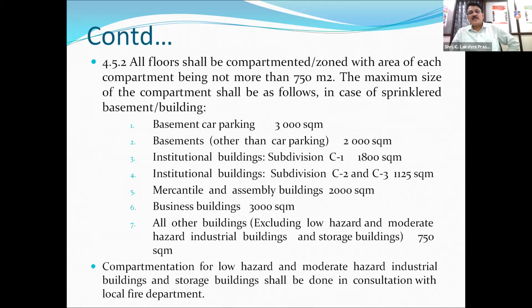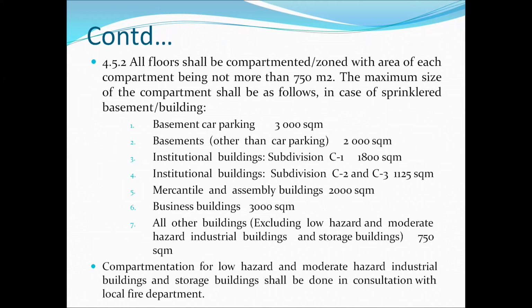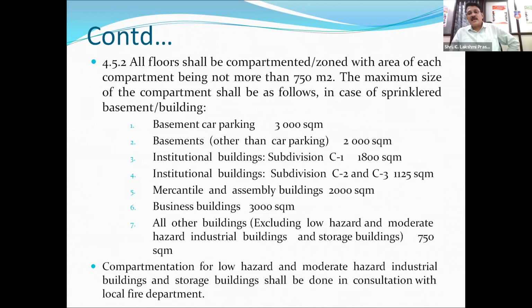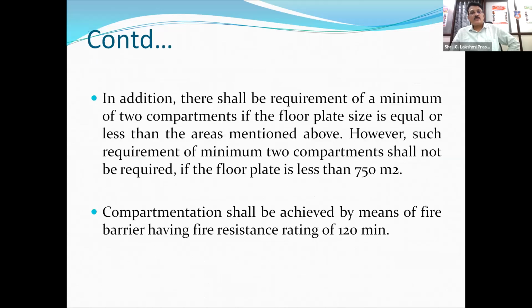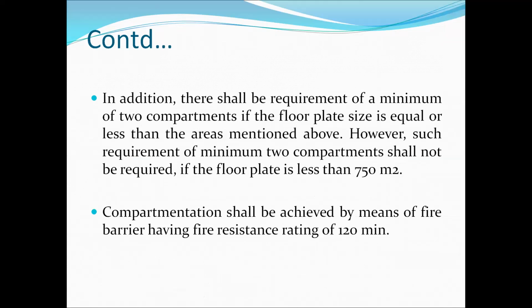Like basements, it is 3,000 square meters. Institutional building, it is 1,800 square meters. Then penal and these custodial institutions. Then there are asylums, it is 1,125. Mercantile buildings, it is 2,000 square meters. Business buildings, it is 3,000 square meters, like that. But a minimum of 2 compartments have to be provided in any building, high-rise building especially, if it is exceeding 750 square meters area, with 2-hour fire rating.